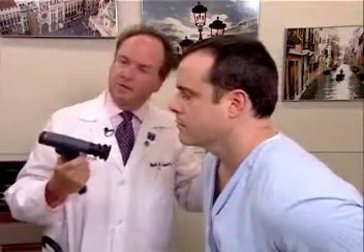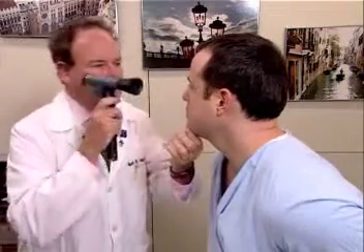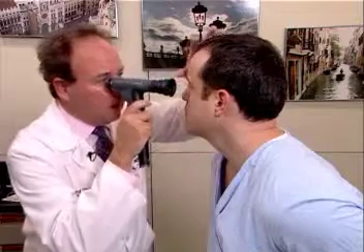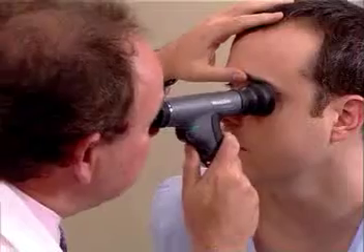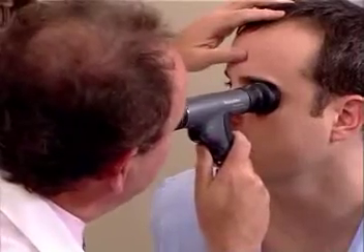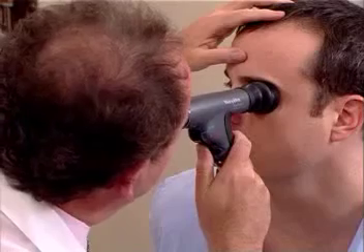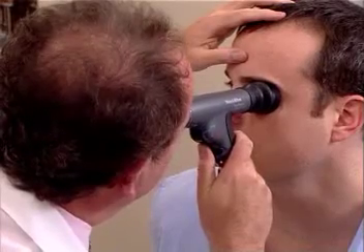A major advantage of this is that many individuals are one-eye dominant and therefore may have trouble using their left eye to examine the left eye of the patient. With the panoptic, if you just turn this way, Mr. Johnson, and look straight in the distance, I can actually visualize Mr. Johnson's left retina by using my right eye, as I'm demonstrating now. In addition, of course, I could use the instrument in my left hand and examine the left retina as well.